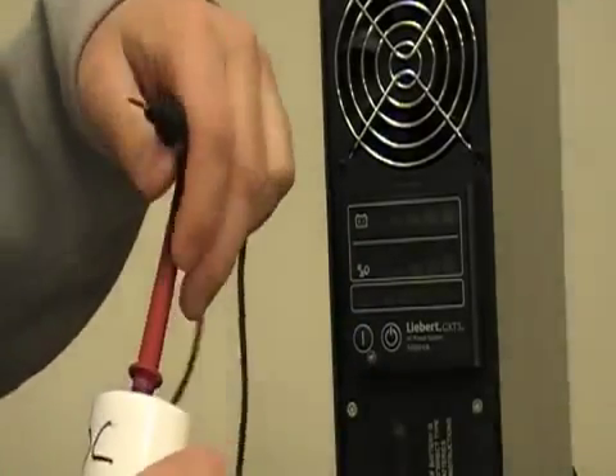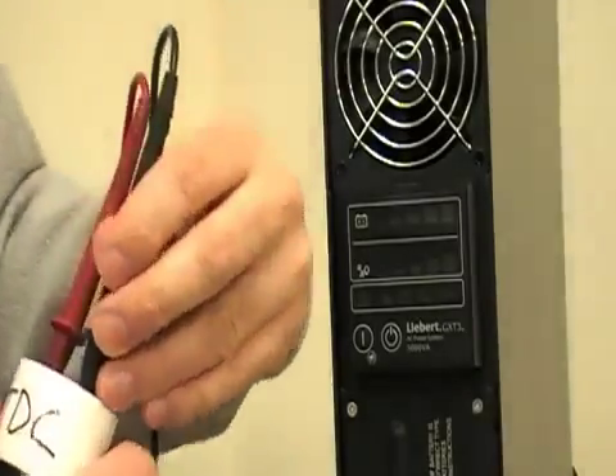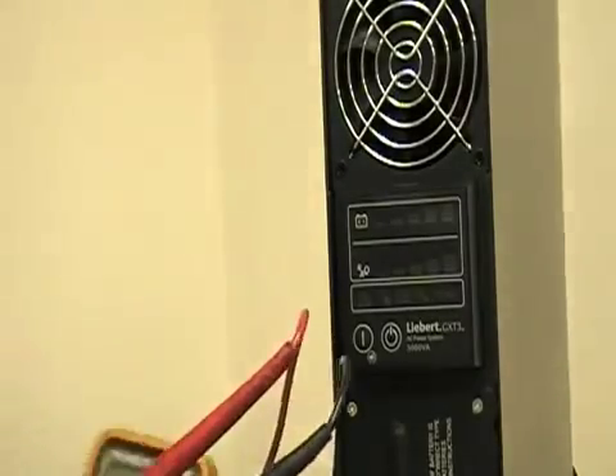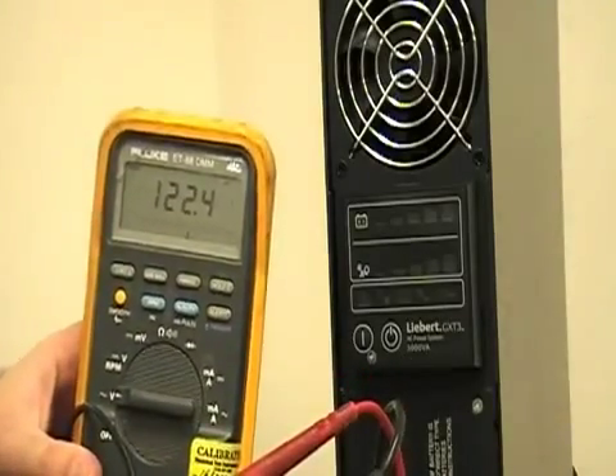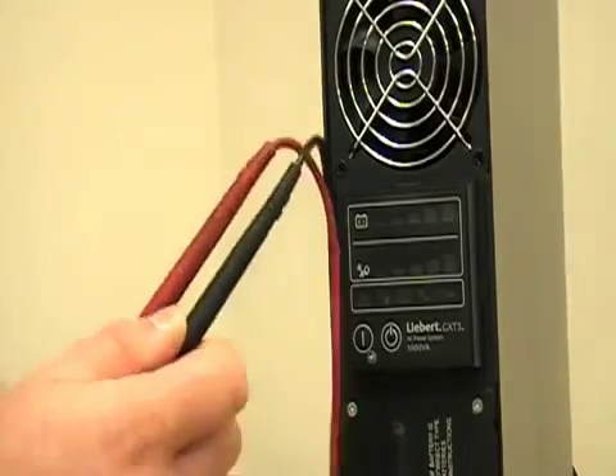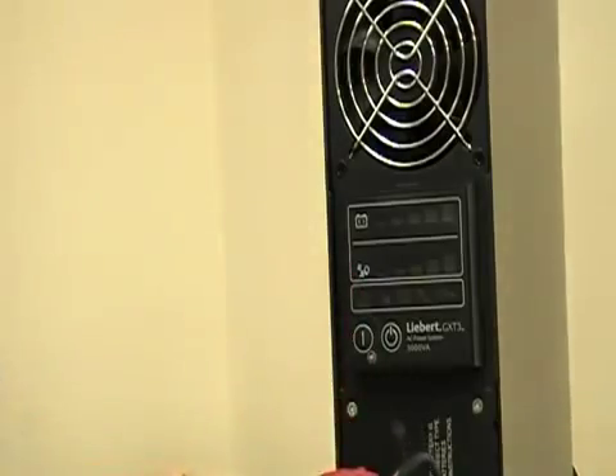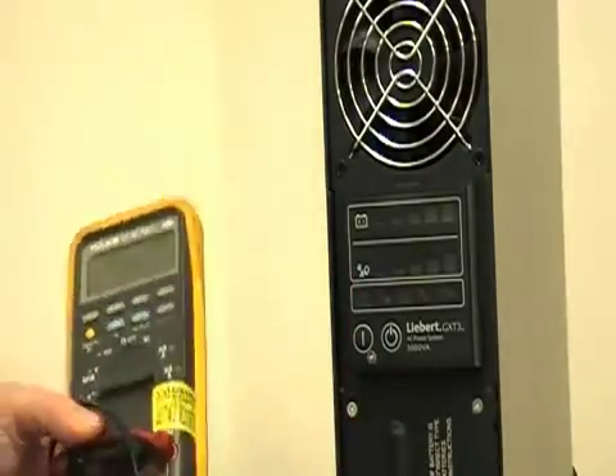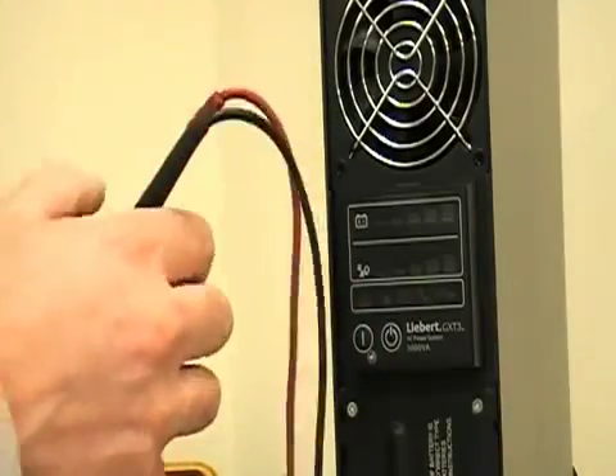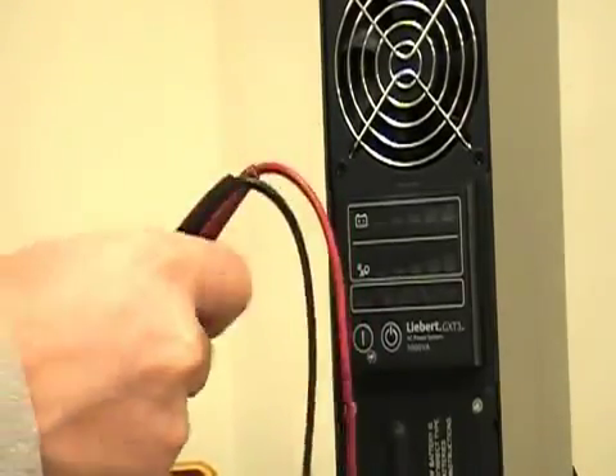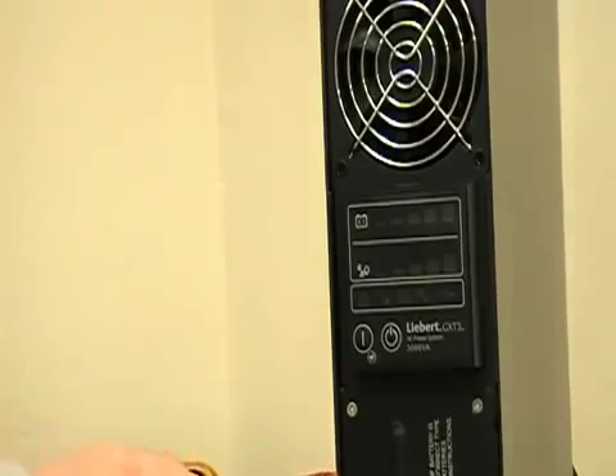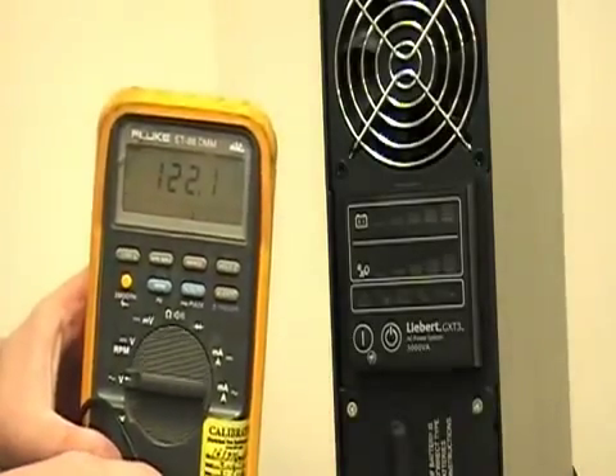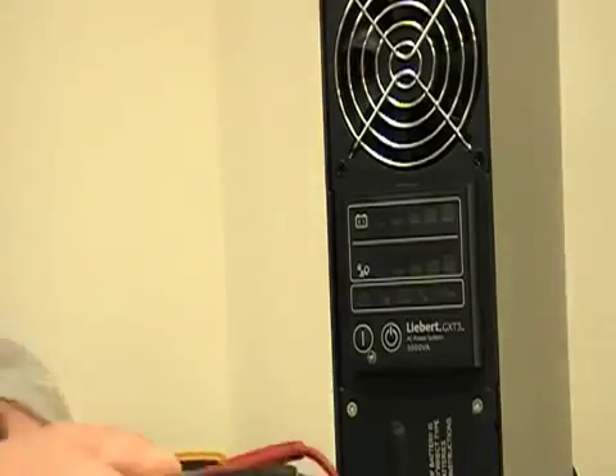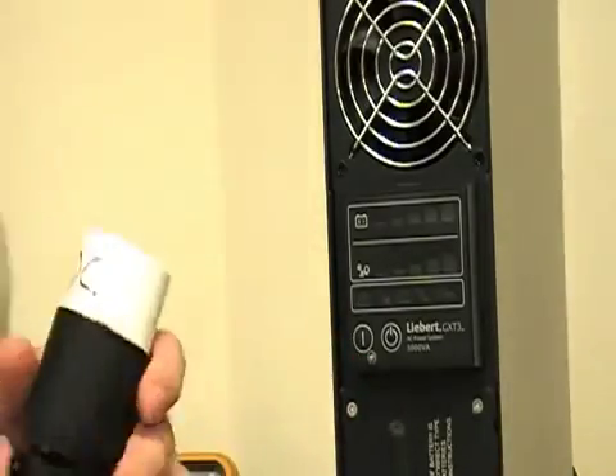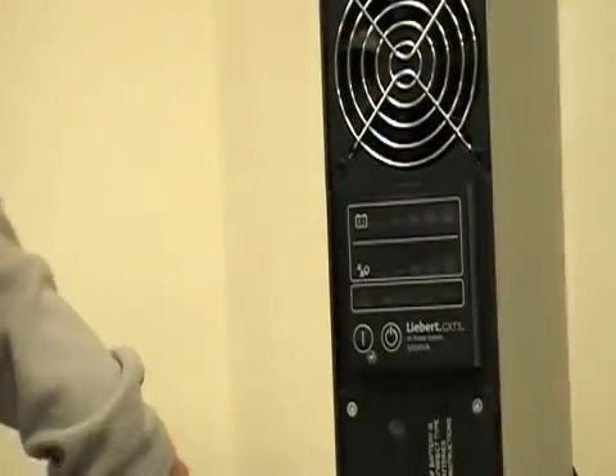So from hot to ground, we should have 122 volts. From ground to neutral, we should have 0. And from hot to neutral, we have 122 volts again. So my plug is oriented properly. It's properly phased out.